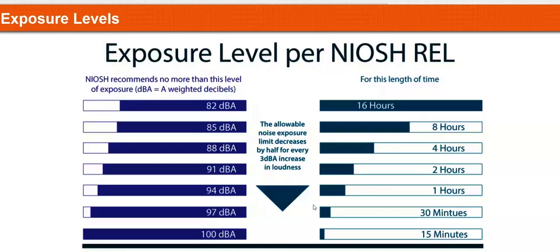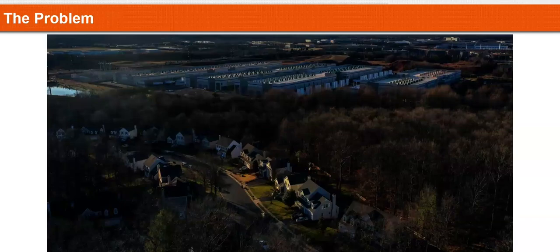So remember that. Anytime you see equipment that has really loud sound levels exceeding 110 decibels, likely you will need some sort of noise control treatment to get acceptable sound levels at a certain line of sight, but also to not damage the public. The image in front of you is the typical description of a problem. It could be a big mall, it could be a massive building with several fans. In this case, it's a data center. But when you look at this right here, you have hundreds of fans.